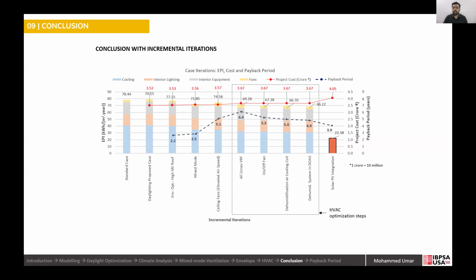Then these are all the HVAC optimization steps I talked about earlier. You can see from the daylight proposed case of 79.1 EPI, which is roughly 25 kBTU per square foot EUI, the optimization strategies were able to bring it down to 66.2 EPI, roughly 21 kBTU per square foot per year EUI, which is a 16% reduction.